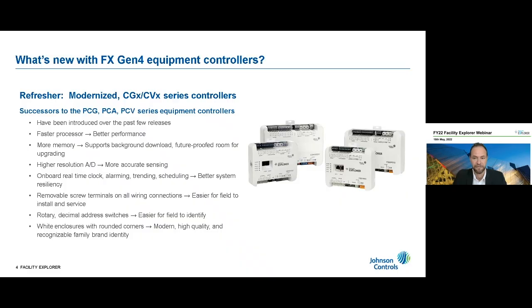Here are key features of these new controllers. First, they have fast processors for better performance. They come with more memory to support useful features such as background downloads, letting you download controller applications without disrupting operation. They have high analog-to-digital resolution for more accurate sensing, and an onboard real-time clock to support alarming, trending, and scheduling at the controller level—offloading the burden on supervisory controllers and bringing better system resilience.